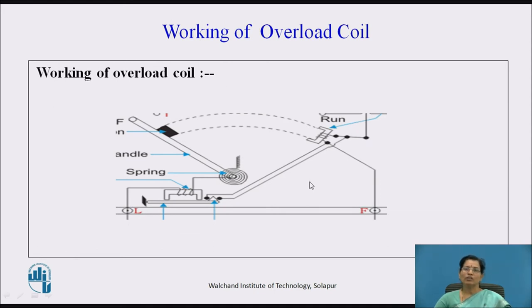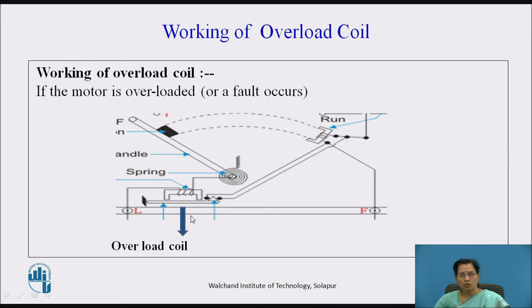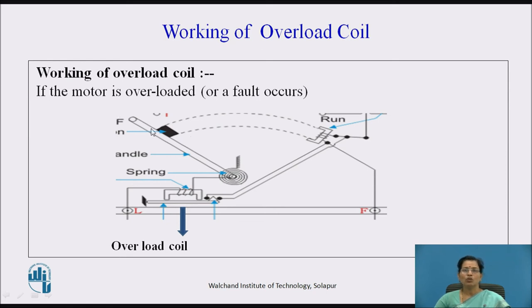Let us see about the working of the overload coil. If the motor is overloaded or a fault occurs, very large current flows through the motor and through the overload coil. Then the overload coil creates a magnetic field for that current. When the arm lifts up, due to the triangular portion, the no-volt coil demagnetizes and the handle goes to the off position. So the overload coil protects the motor from overload current.